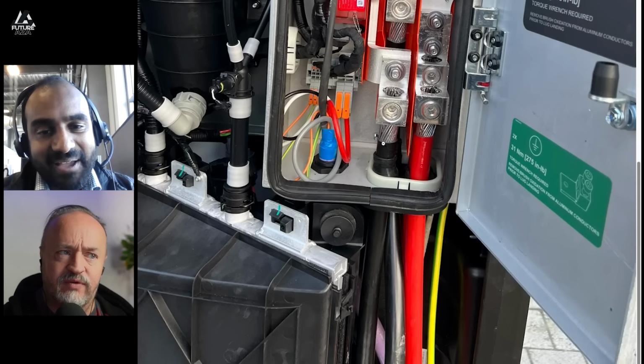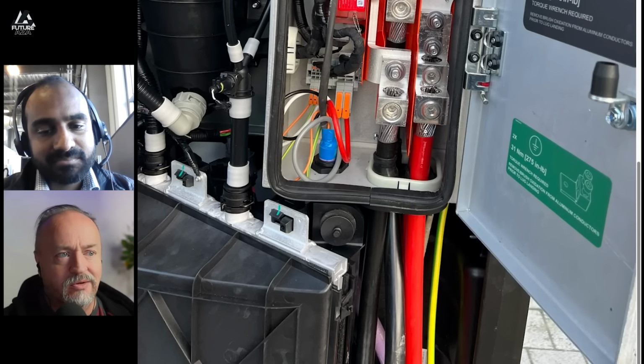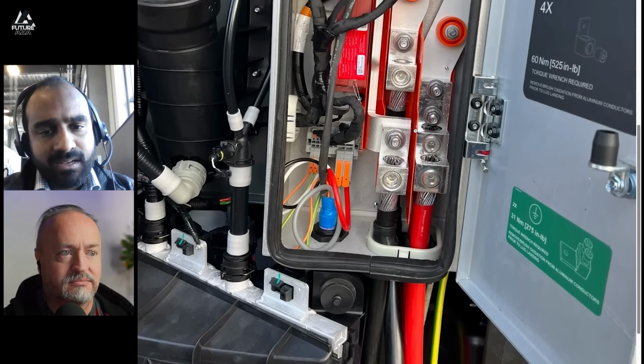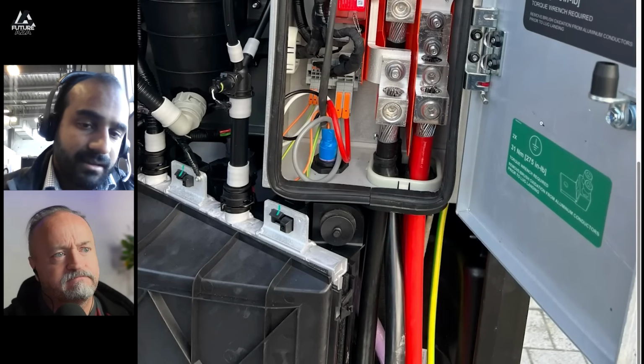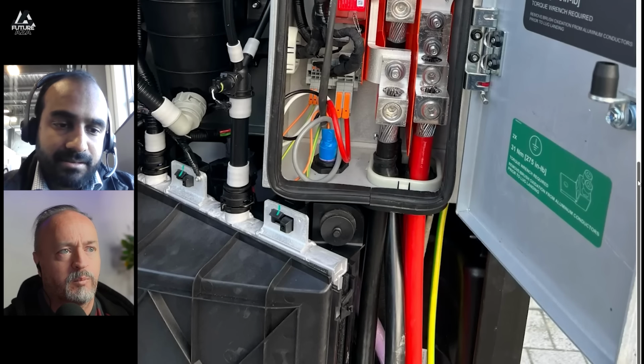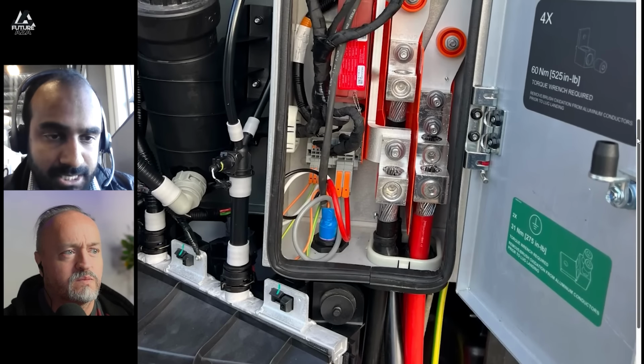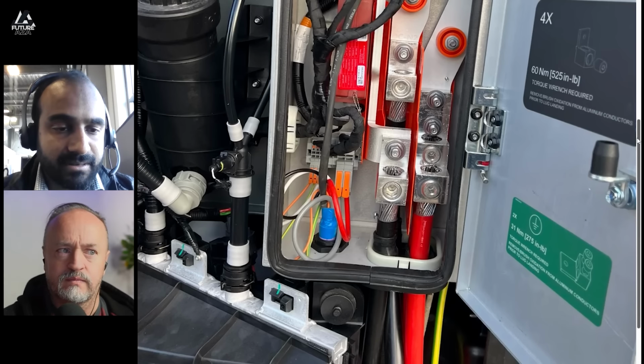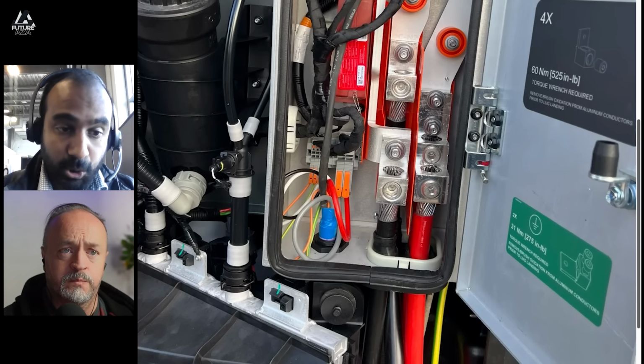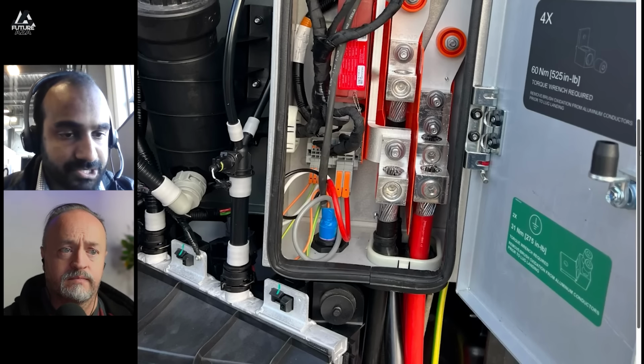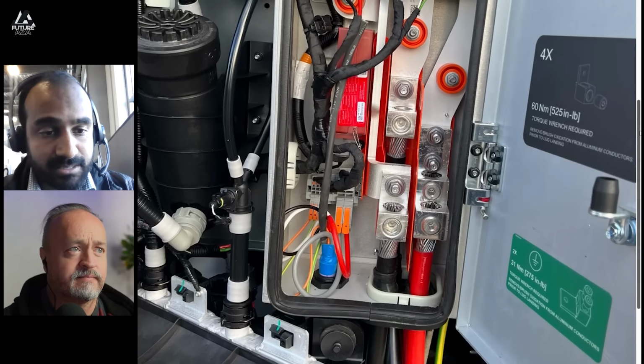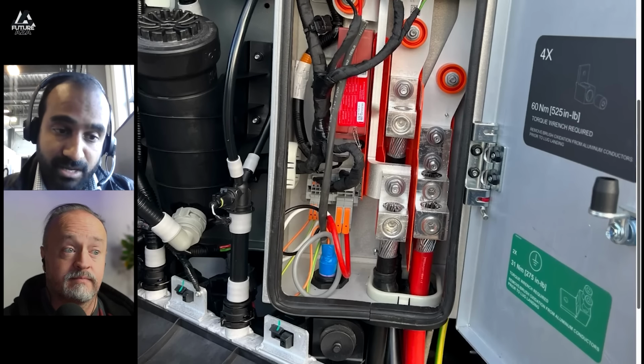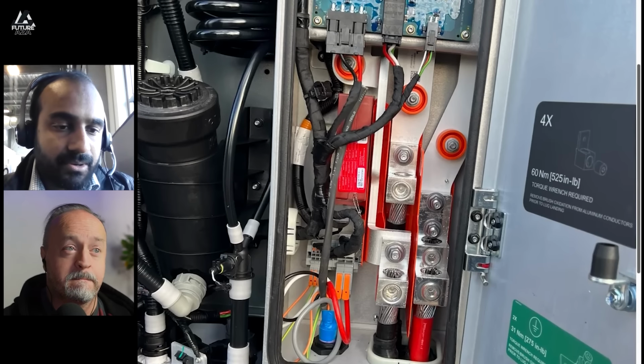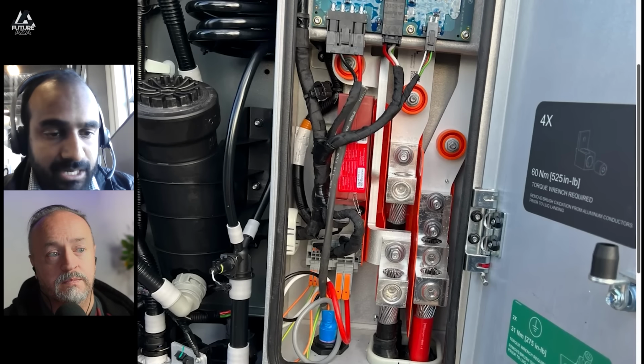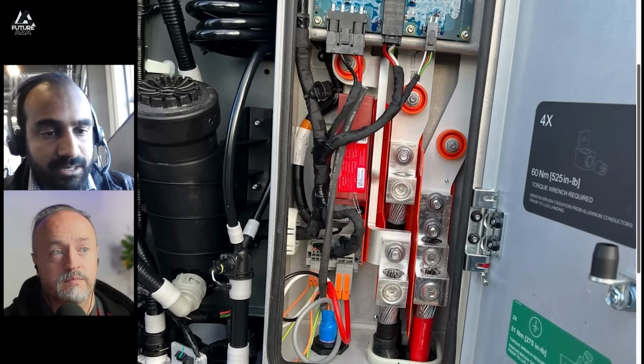Question for you - these high voltage cables coming in don't look like copper. No, that's probably aluminum. You can use aluminum - it's less conductive than copper, so you lose a little efficiency, but what you get back is cost, since aluminum is way cheaper. We do this too - we actually run aluminum in conduit if we can.